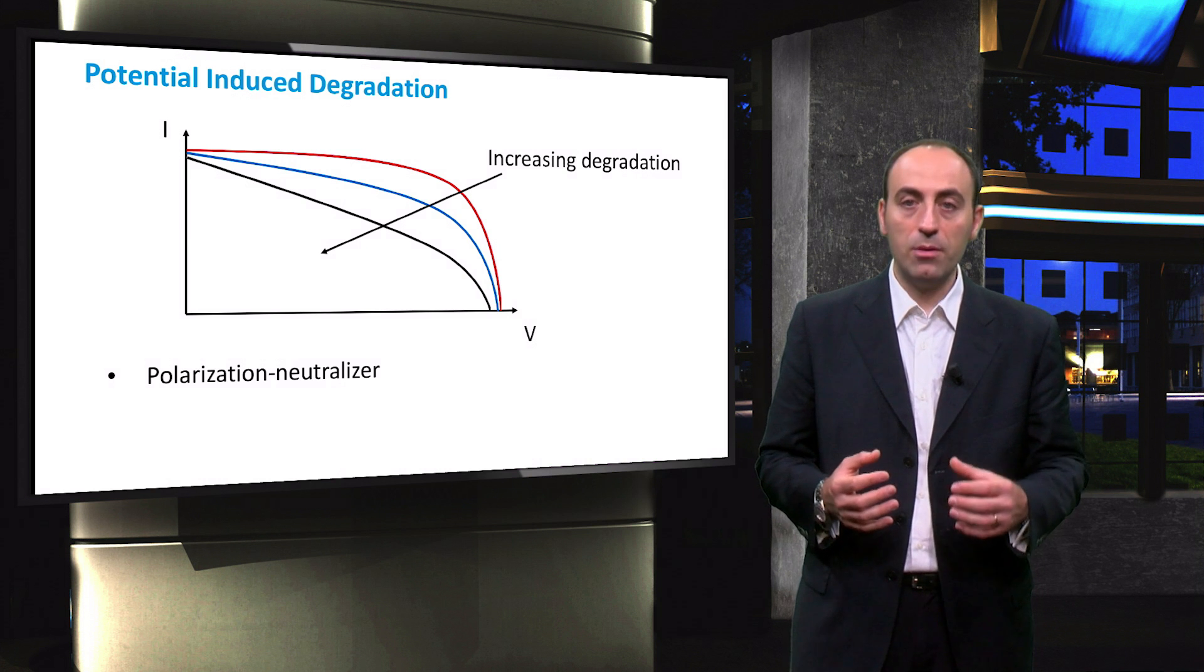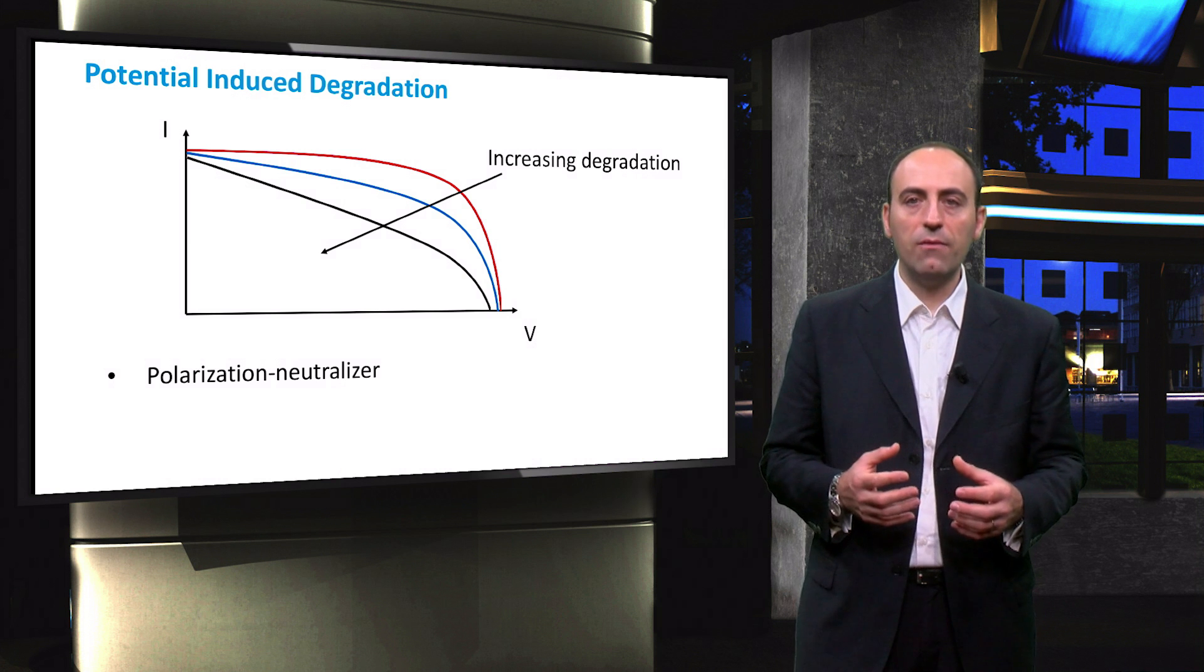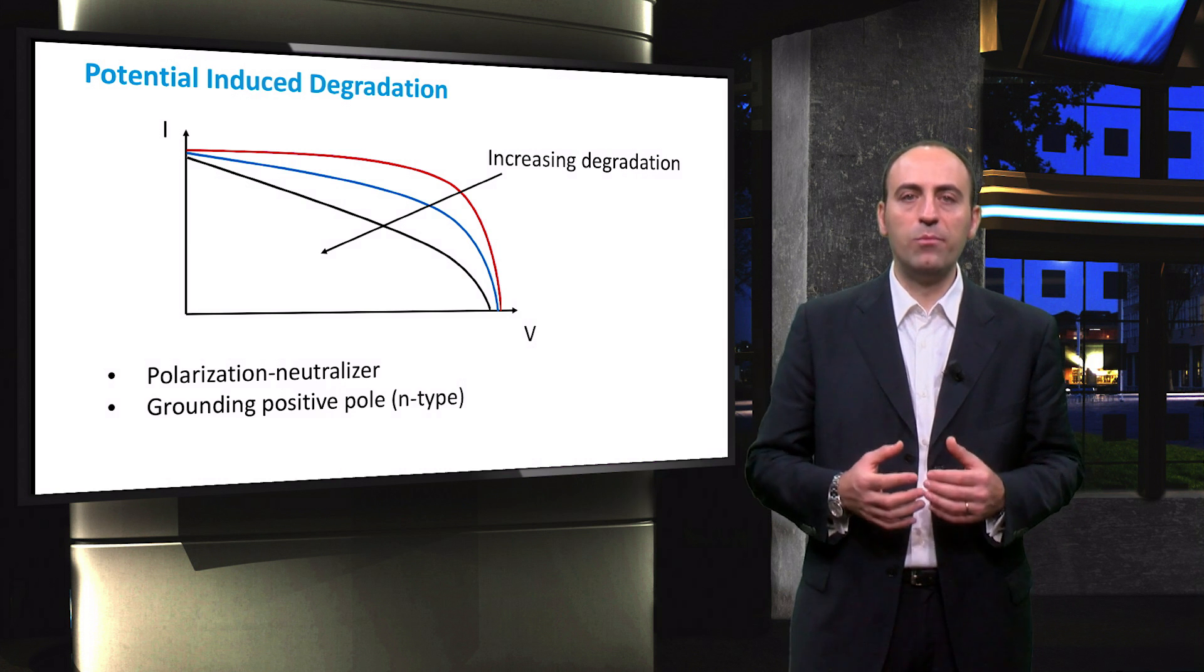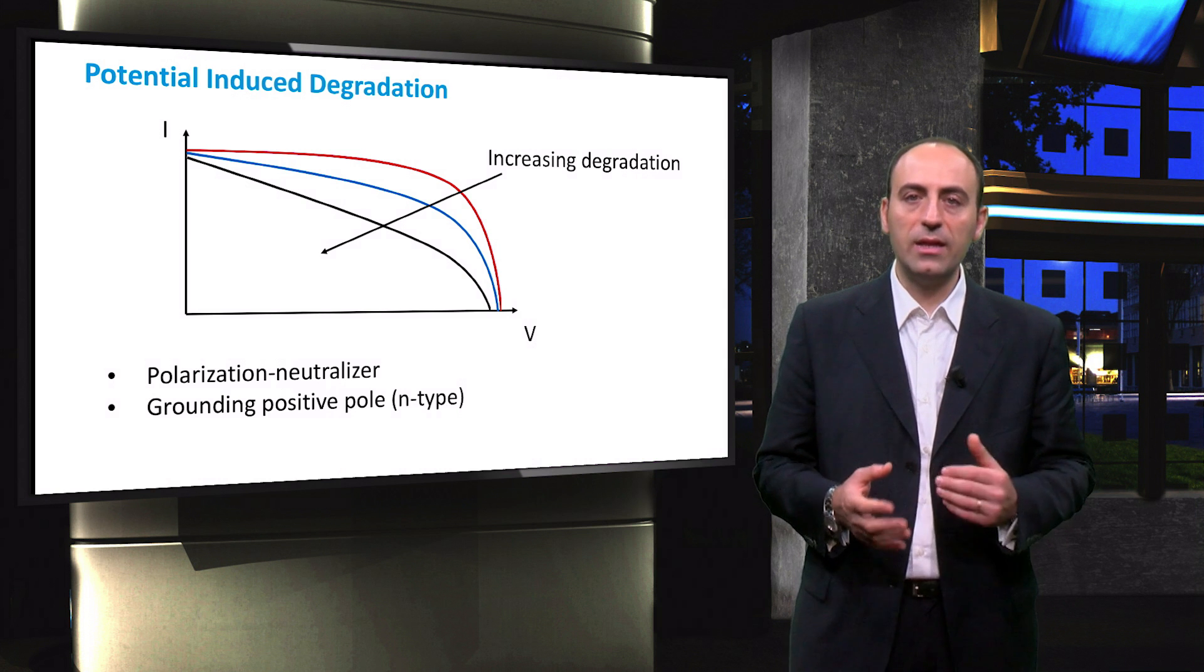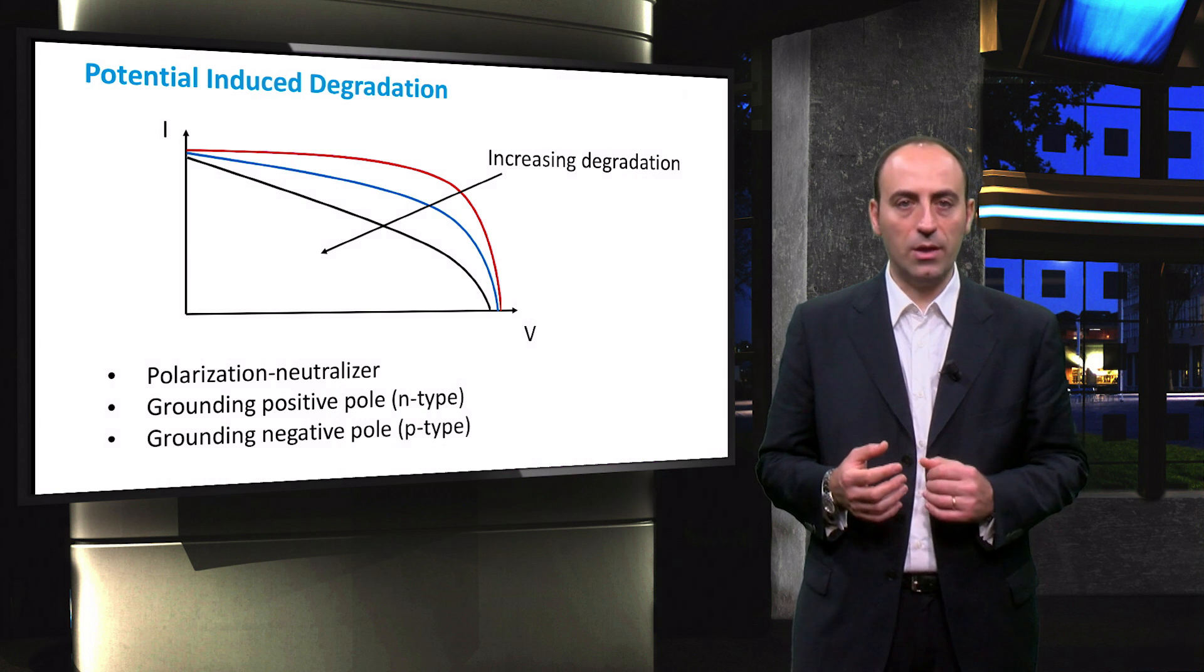If grounding can be performed, we have to differentiate between the two cases. If the wafers of the PV panel are n-type, then the positive pole should be grounded. On the other hand, if the cells are of P-type, the pole to ground is the negative one.